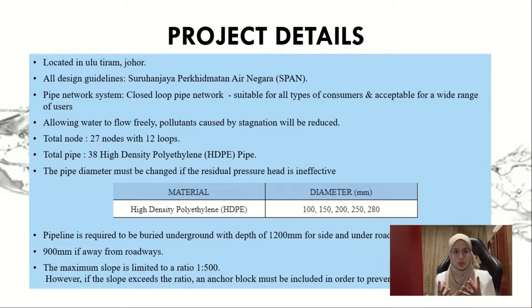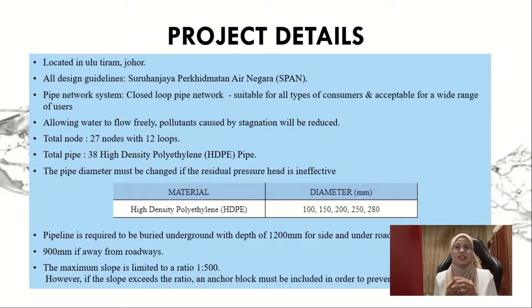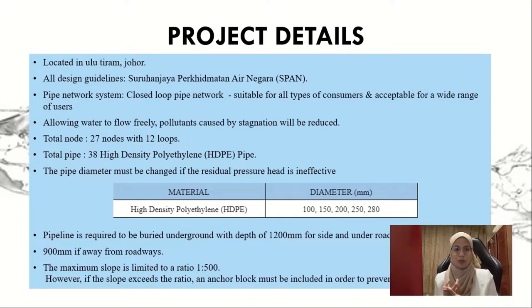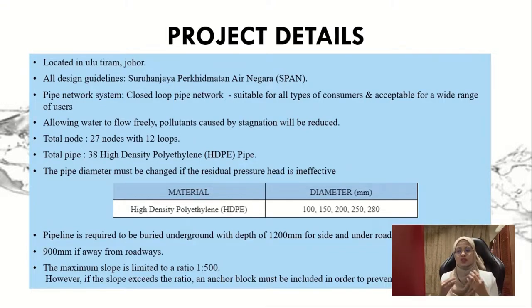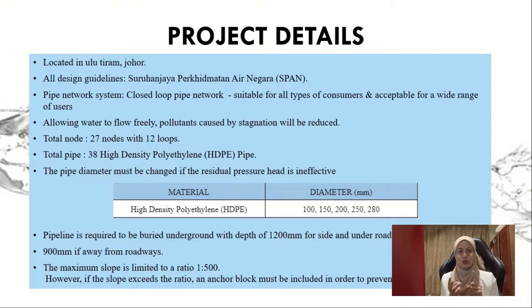For example, if one pipe in the proposed site is broken or damaged and needs to be stopped for maintenance work, other consumers will still receive water supply through the closed-loop pipe network system. We also use a variety of pipe diameters because the size must be changed if the residual pressure head is ineffective. The diameters used are 100 mm, 150 mm, 200 mm, 250 mm, and 280 mm — overall five pipe diameter sizes.